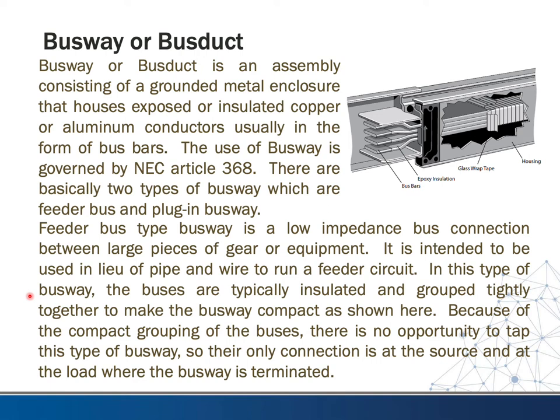Busway or bus duct is an assembly consisting of a grounded metal enclosure that houses exposed or insulated copper or aluminum conductors, usually in the form of bus bars. The use of busway is governed by NEC Article 368. There are basically two types of busway, which are feeder bus and plug-in busway. Feeder bus type busway is a low impedance bus connection between large pieces of gear or equipment. It is intended to be used in lieu of pipe and wire to run a feeder circuit.